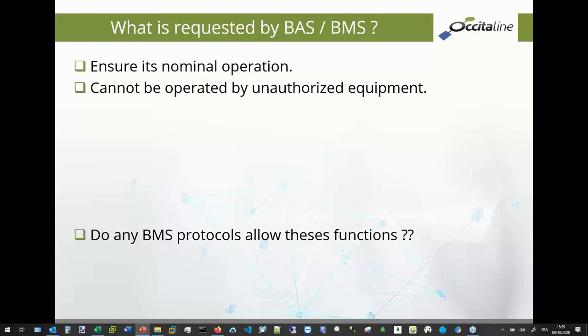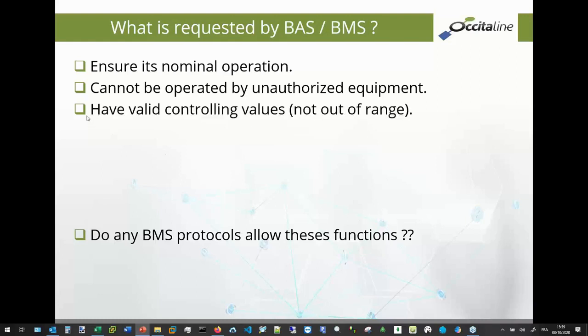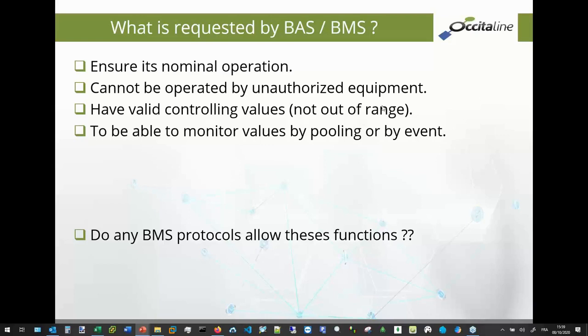What is really requested by the BAS or the BMS? In fact, the first very important thing is to ensure its nominal operation. Nominal operation is working for the comfort, for the light, for access control, and so on. Second point, from my point of view, it cannot be operated by an unauthorized equipment or operator. It's very important. If you receive an opening command for each door of the hotel, it's not good.